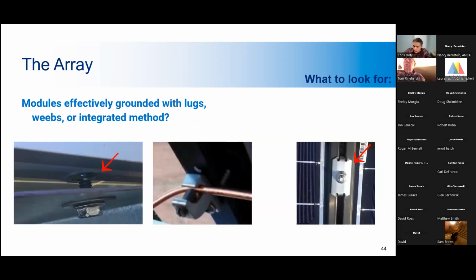All right. Another thing you want to look for with the array is the grounding of the array. The grounding and the bonding of the array is not only a code issue, but a safety issue. The integrity of the grounding system is vital to any electrical installation, not just PV, and it's dependent not only on the conductors, but also on the equipment itself, which is used to carry fault current to an overcurrent protection device or a fault detection system. In the event that there's a breakdown anywhere along the ground fault path, the fault will not be detected, and this can leave parts of the system conductive and energized and presents a significant shock hazard.